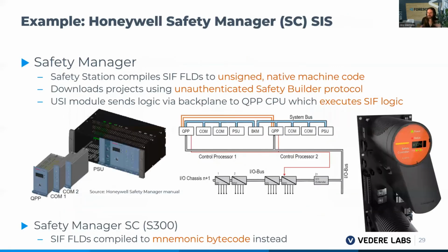Another example of differing impact is the Honeywell Safety Manager SIS, a SIL3 safety controller used in various critical applications, similar to the Schneider TriConex. The engineering software, called Safety Station, compiles safety instrumented functions, essentially safety loop diagrams, to unsigned native machine code, wraps it in a project file format, and downloads it to the controller using an unauthenticated protocol called Safety Builder.